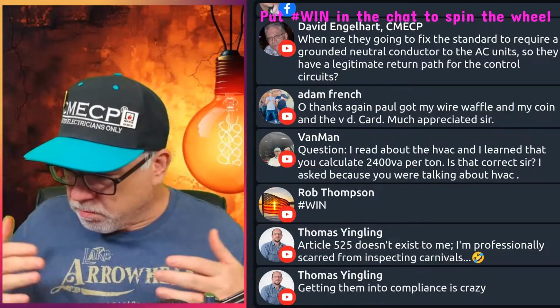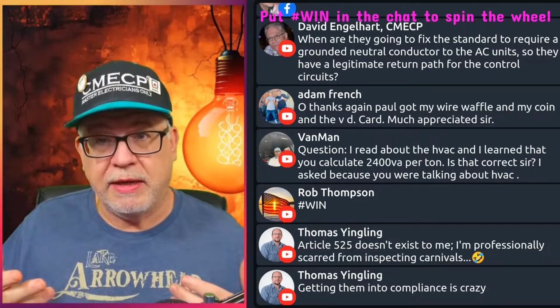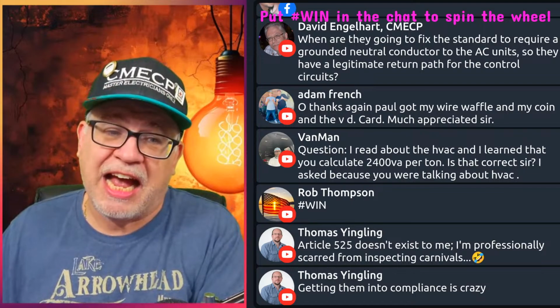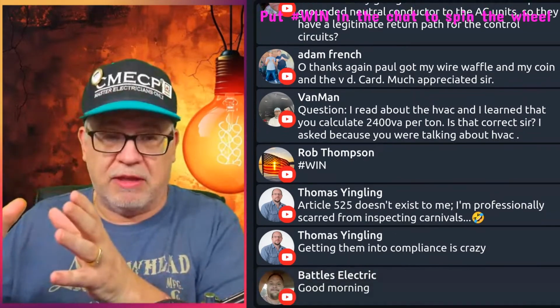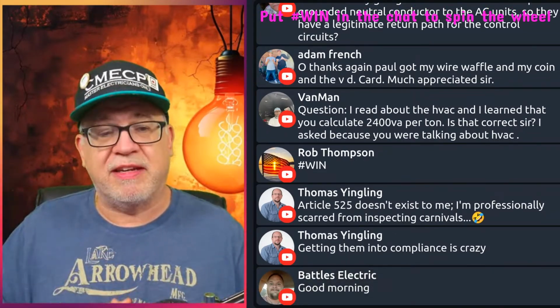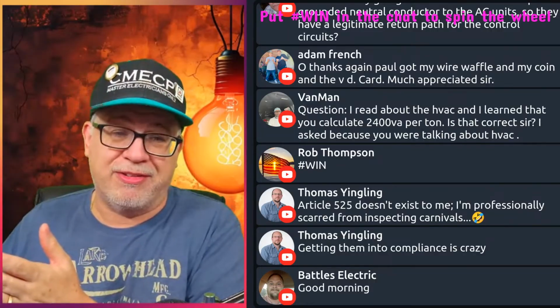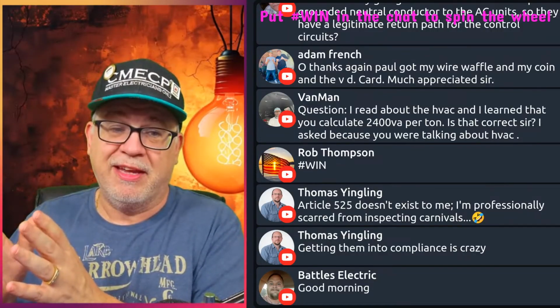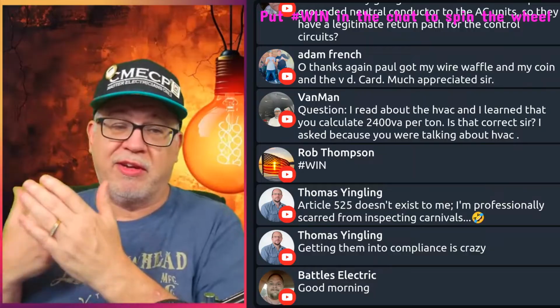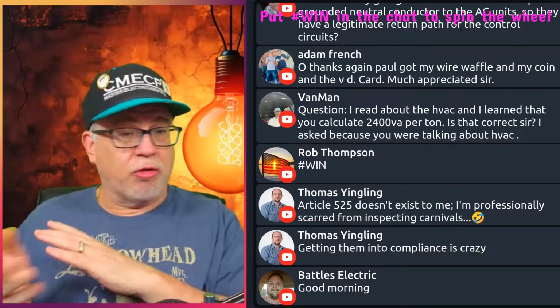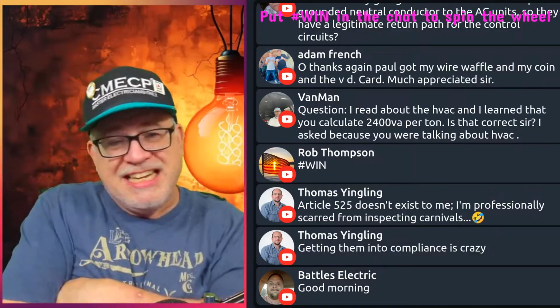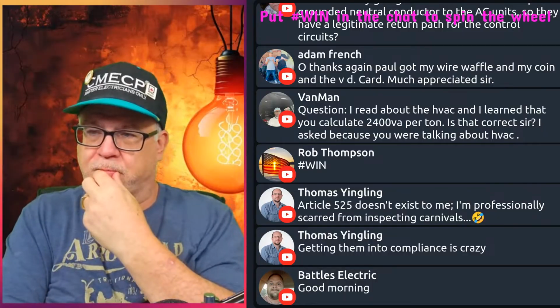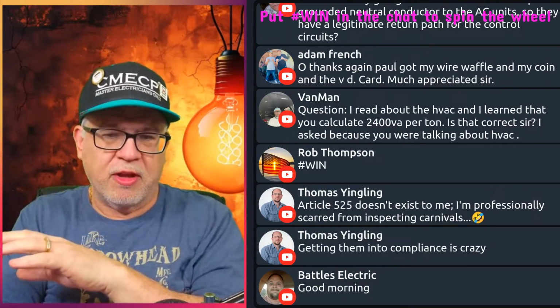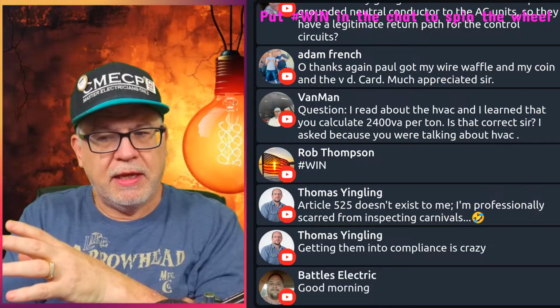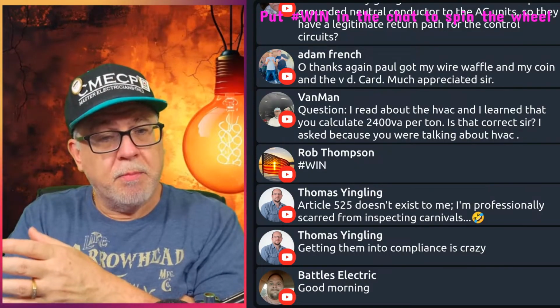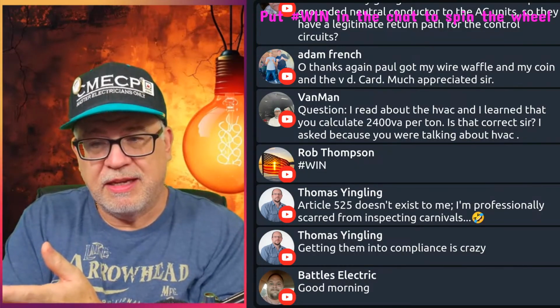Now, the only exception to that is what? If you put the EVSE outside and it constitutes being an outlet, then you go back to 210.8(F), and that would require the GFCI protection. Make sense? If it was a receptacle, it requires GFCI protection either way, garage or outside, doesn't matter. So, significant change. Now, for the 2026, they are going to introduce the requirement for permanently wired EVSE anywhere.